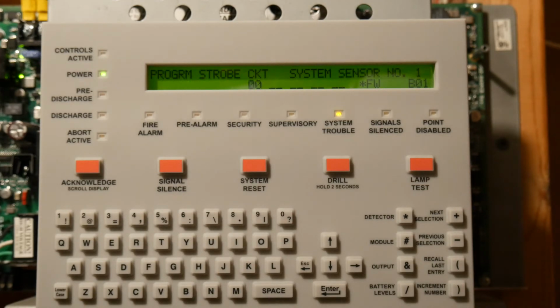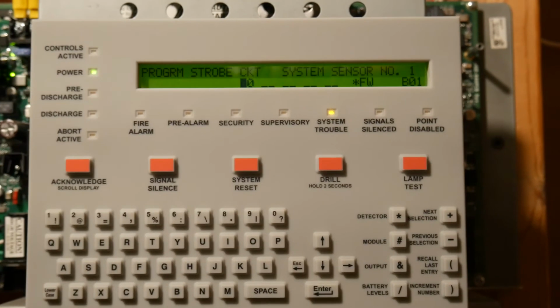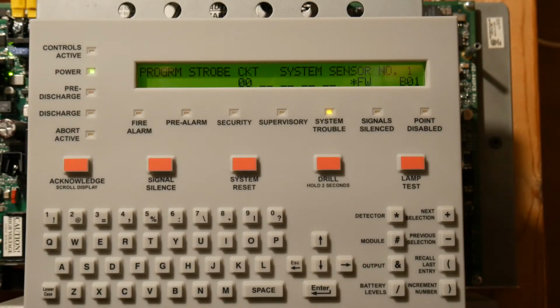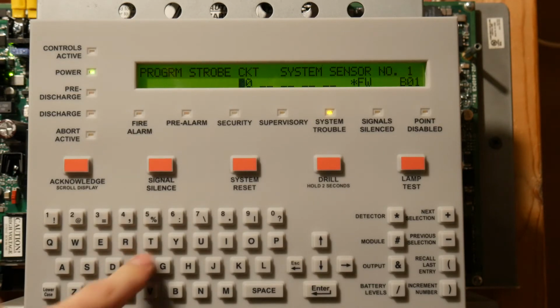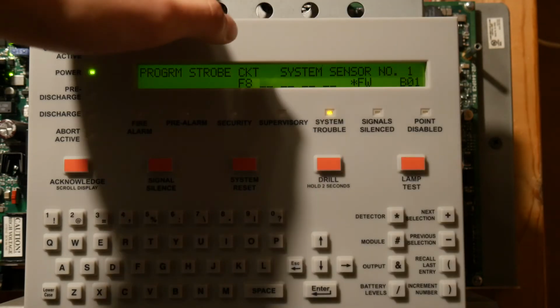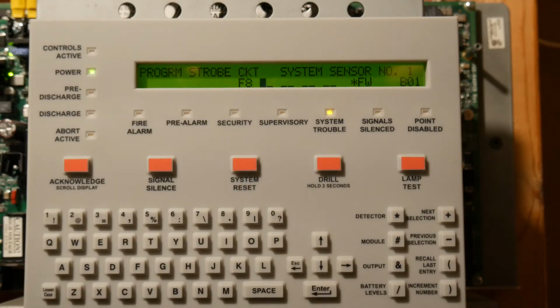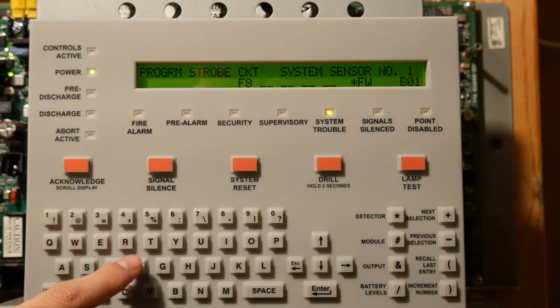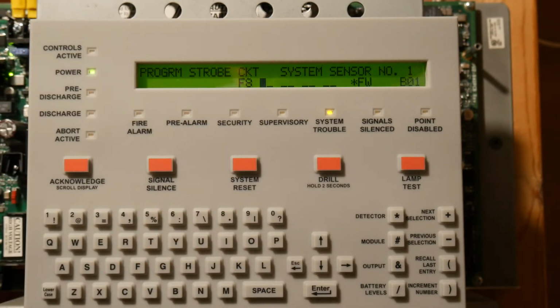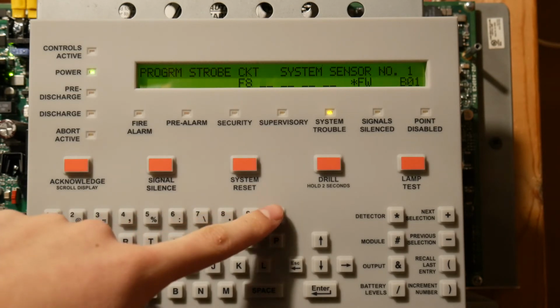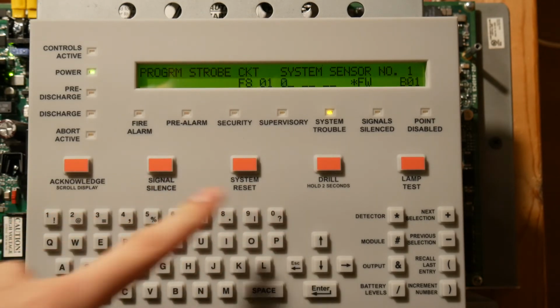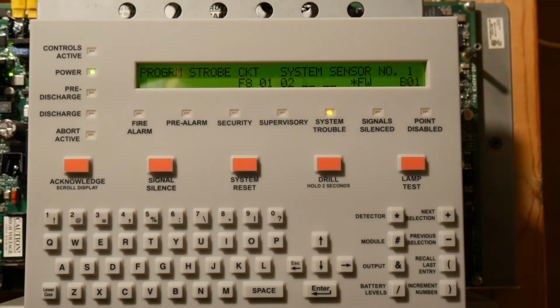Sadly, with this panel, with all Notifier panels, let's say you want one NAC as March time and one NAC as code 3. Sadly, you cannot do that. Since special functions is used for NACs, you can only set your special function for one thing. So for system sensor sync, I can only use system sensor sync. But as you can see, I set F8, function 8, for system sensor coding. And now I want zone 1 and zone 2 to activate this. So we'll put that and we'll scroll here.